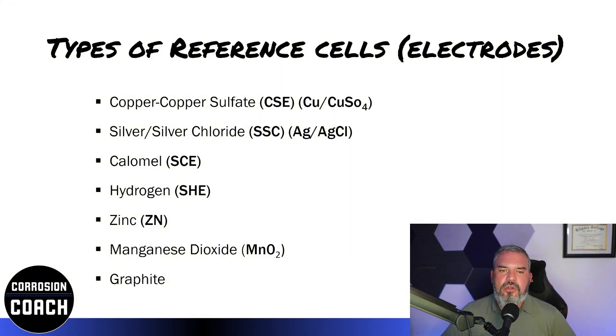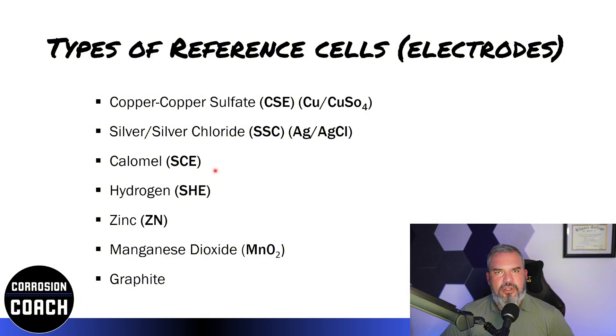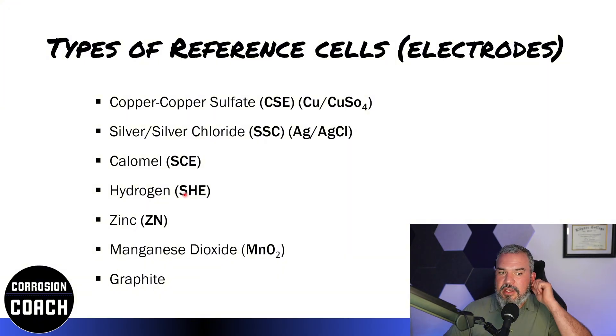If we're in an environment where the soil happens to be salt water, we can use a silver-silver chloride reference electrode — that's the second bullet point. You might also hear about the calomel and hydrogen electrodes. Those two in the middle are not really used in the field; they're used in a lab setting. For example, a university lab running controlled tests would want a very stable reference electrode with accurate readings, and they'd use calomel for that.